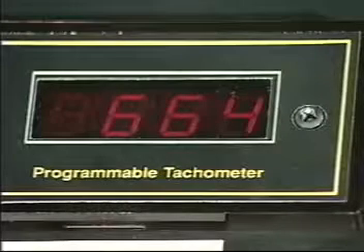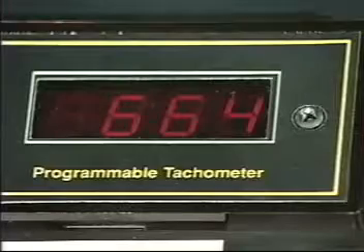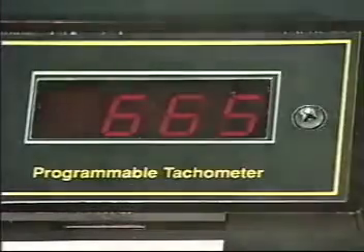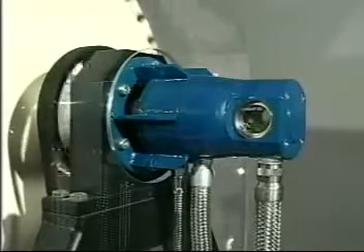When the dryer speed is increased to 330 feet per minute, the condensate begins a light cascade. As the dryer speed is increased above 330 feet per minute to 660 feet per minute, the condensate starts to cascade. In both condensate behaviors, the stationary siphon is efficient at removing condensate from the dryer because the pickup shoe remains dipped in the condensate. The efficiency of the rotating siphon will also increase somewhat because the pickup shoe is in contact with an increased amount of condensate.